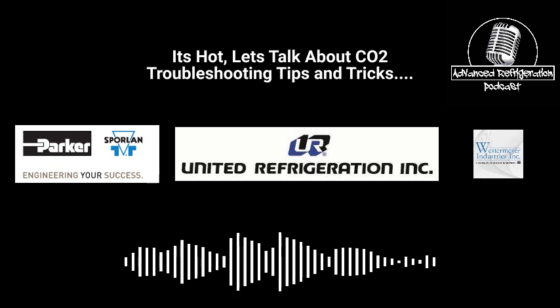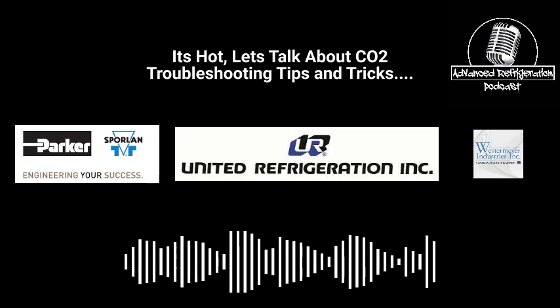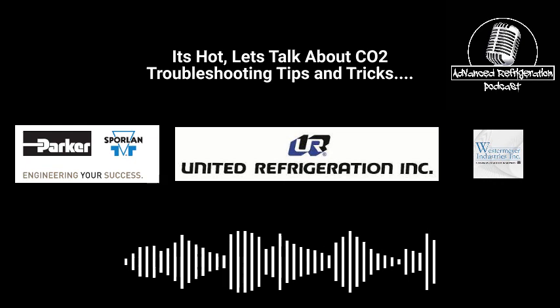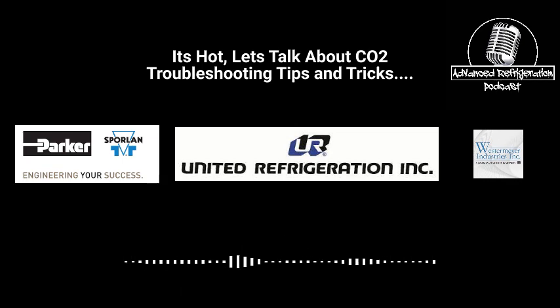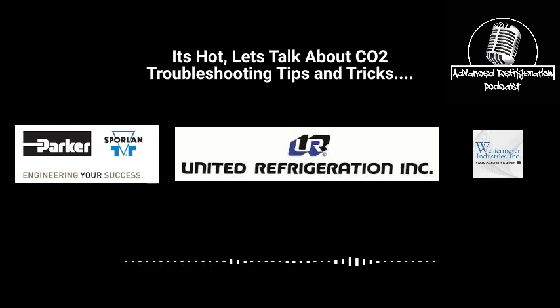Those MT case controllers do a really good job of controlling superheat, though. They do a phenomenal job, and they are super easy to tune once you get the suction steady. But that suction is key, because if you've got that hunting going on, you're going to have head pressure issues too, guaranteed. Medium temp suction hunting causes the receiver to hunt, which is going to cause that HPV to start closing down. If that receiver starts hunting, I guarantee you the HPV is going to start hunting with it.